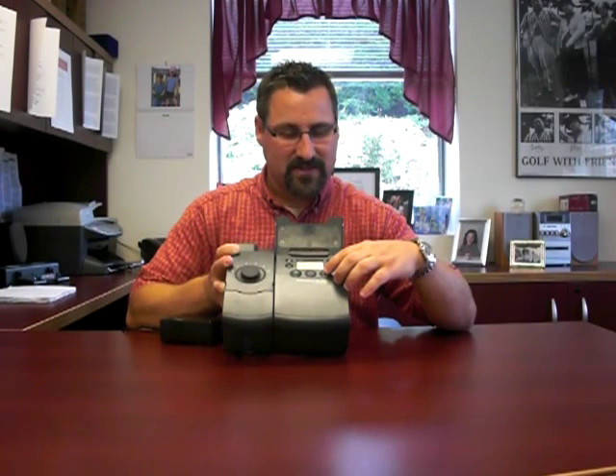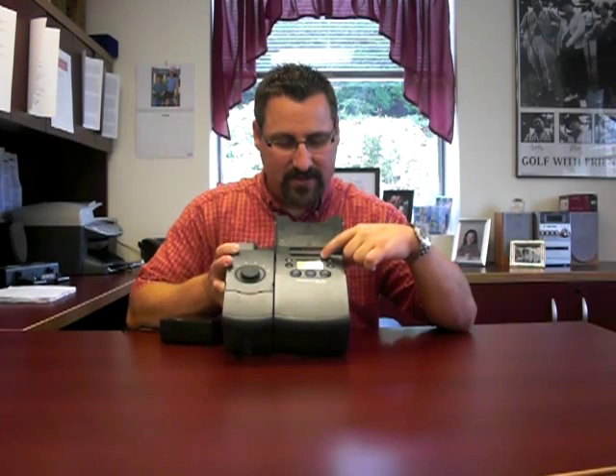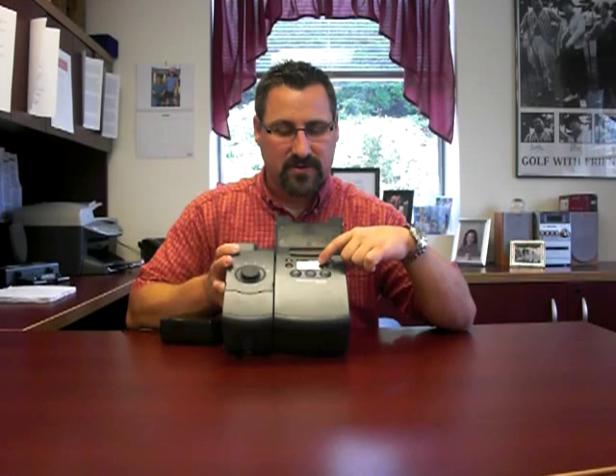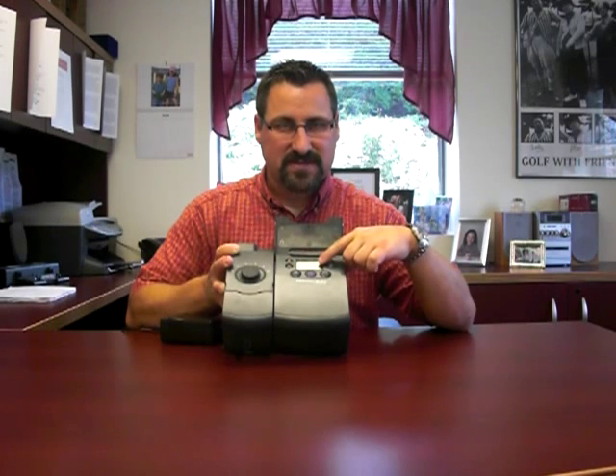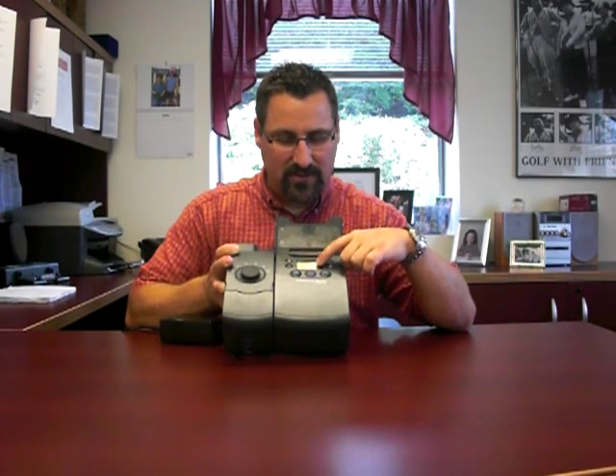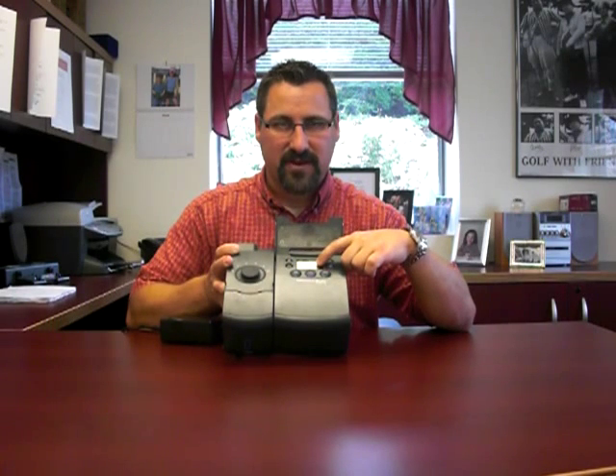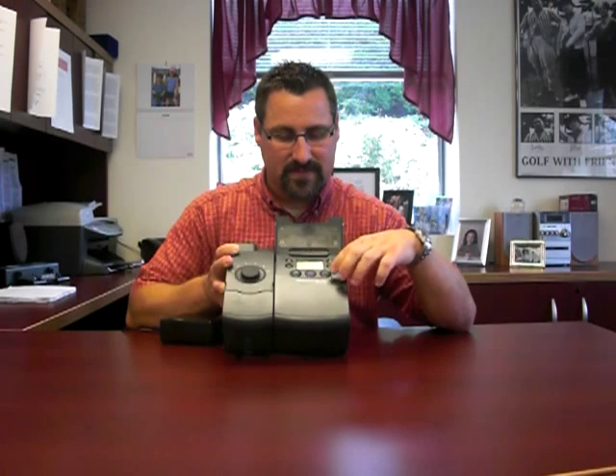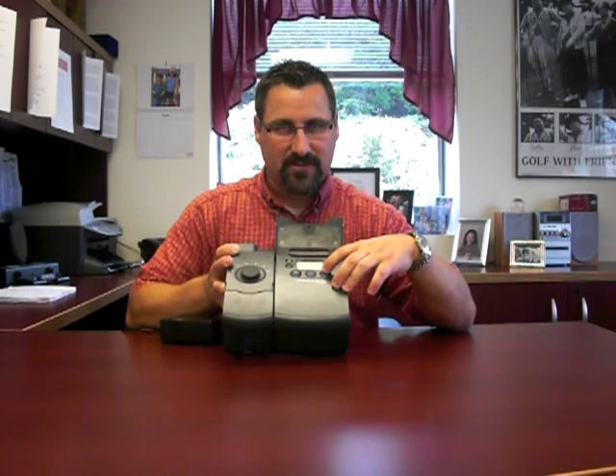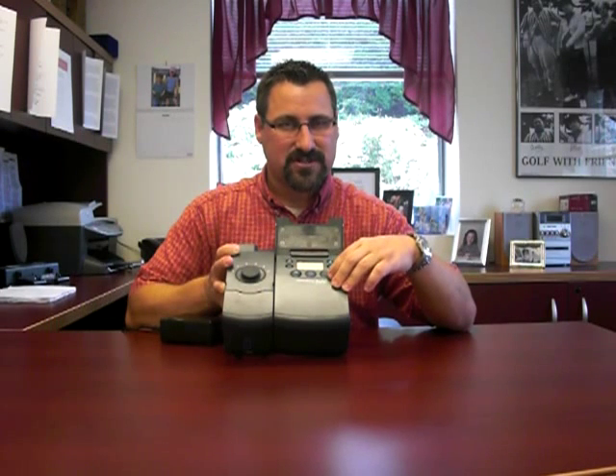If you happen to hit the C-Flex button, you get a screen that says C-Flex setting, and there's numbers 1, 2, and 3. Those are the levels of C-Flex we can set. The higher the setting, the more relief you get. You'll see a little arrow that's blinking above one of the numbers. That's showing you what it's currently set at. Those levels can be changed by simply hitting the C-Flex button again, and you'll see that little arrow jump. We can set that to 1, 2, or 3, and we will set that at your setup time. If you want that changed, I advise you just to talk to the respiratory therapist and get their opinion on changing that. And we can help you do that as well if you would like to.